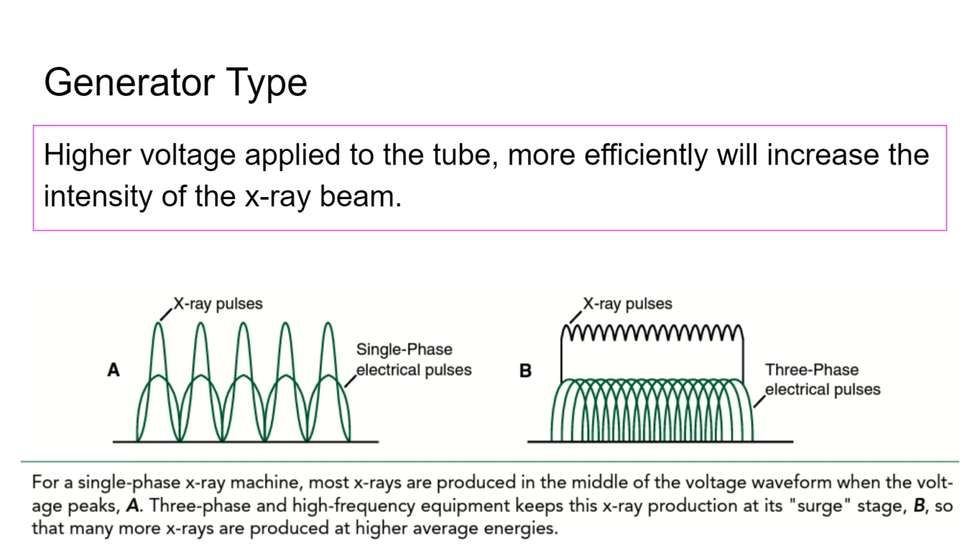I use a much lower exposure in this room with a high frequency generator, and that's due to something known as ripple. I'm not going to get into exactly what ripple is, but the less ripple you have, so ripple down, efficiency up. So very low ripple on the right side here, much higher here. Each one of these is giving you an X-ray, right? So you're essentially getting good, or good enough, radiographic result without using that much radiation.